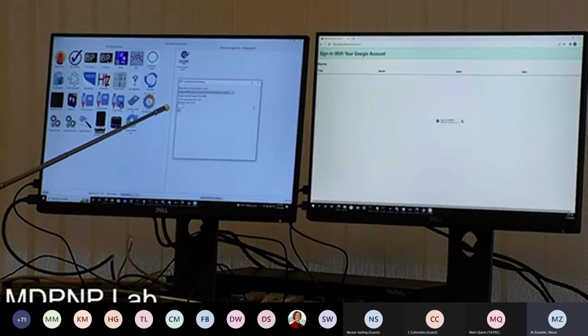And we can see what the current infusion rate is, that it's 25. And we have a box here where we can set that. So we're going to type in a new rate of 30, click set, and that will go through and change the rate of the pump to 30. That usually takes a few seconds to go through. The beep from the pump means that it's received the command, and now it's running at a rate of 30.